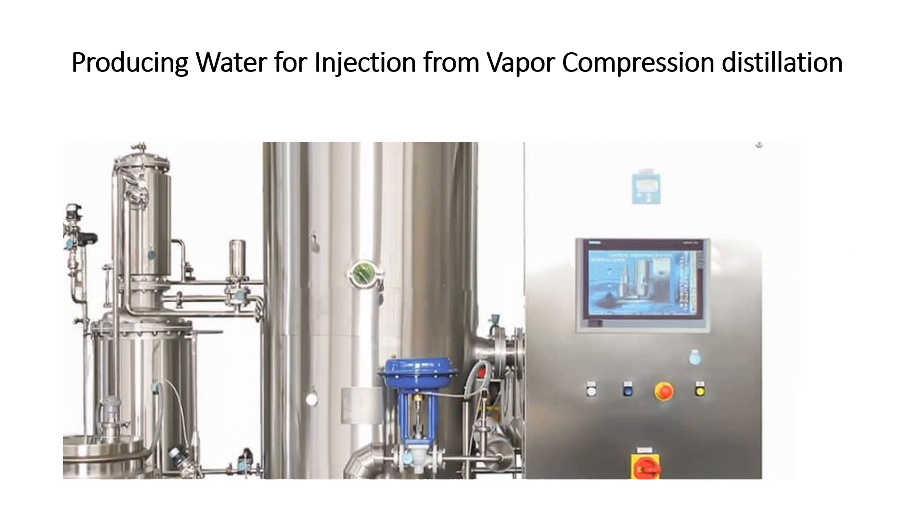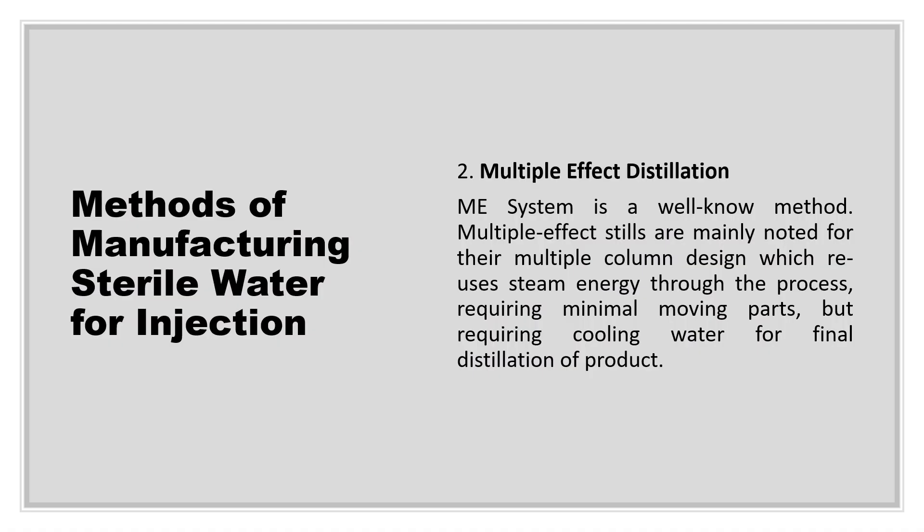This is the unit for vapor compression distillation — you can see the vapors being compressed using steam or electrical energy. The second widely used method is multiple effect distillation. The principle remains the same: vapors are condensed and water is formed. Multiple effect distillation is noted for its multiple column design, which reuses steam energy and requires minimal moving parts but requires cooling water for final distillation. Water for injection is generally kept at around 80°C as formed, to maintain sterility during formulation.